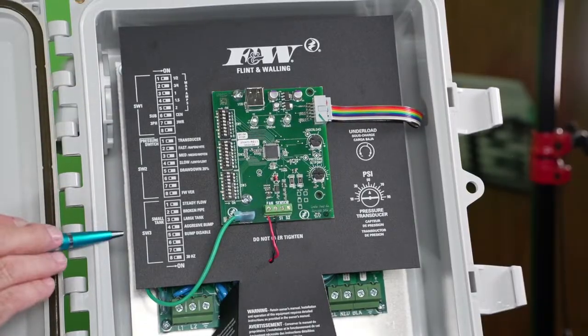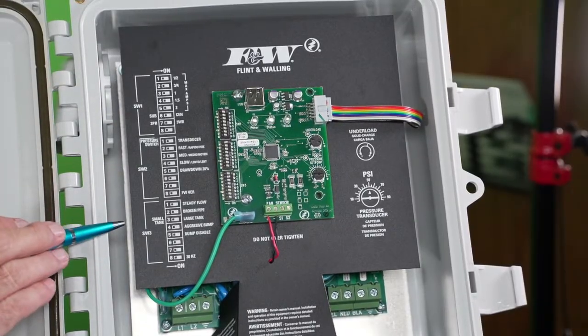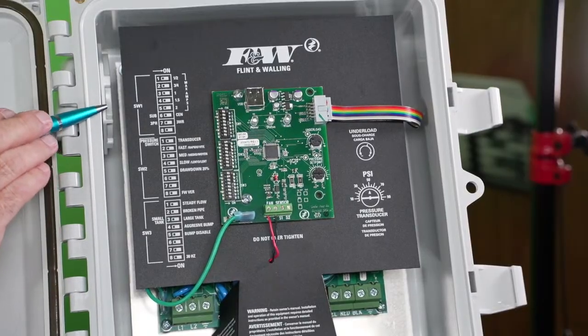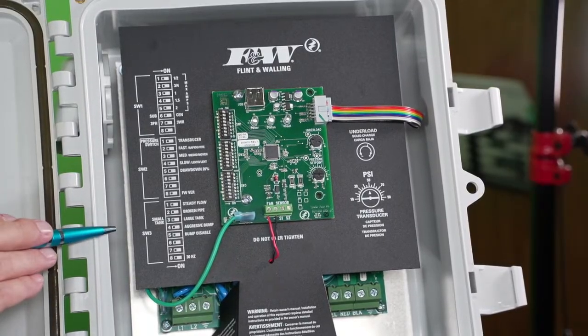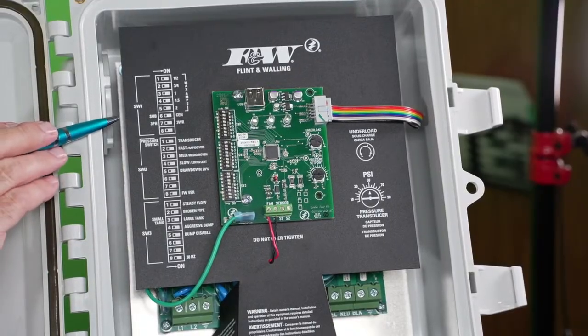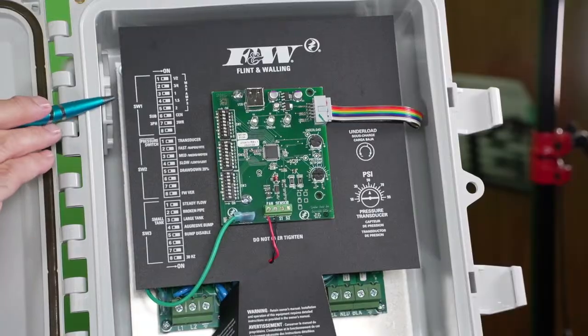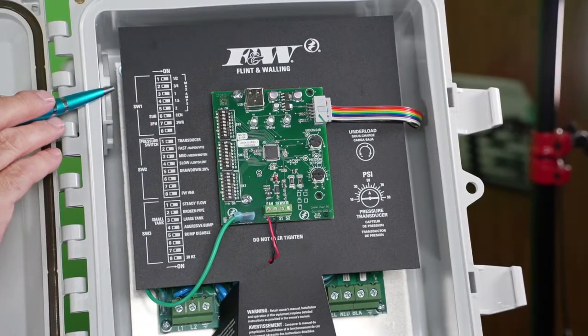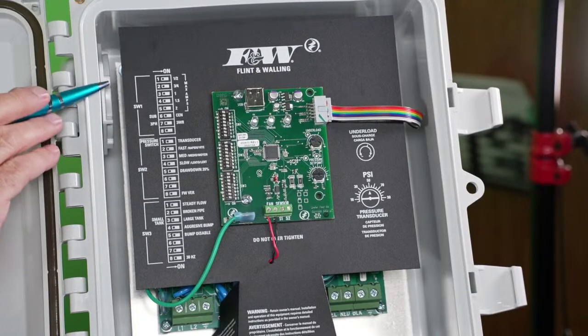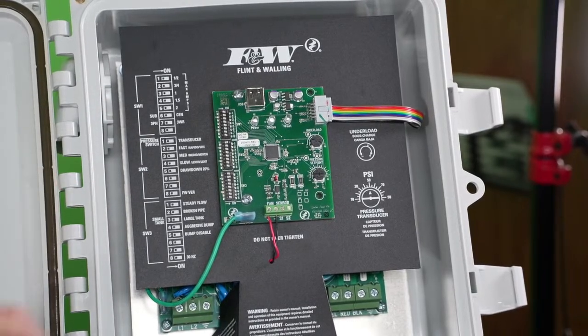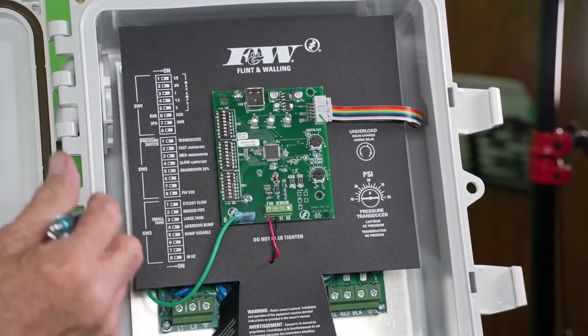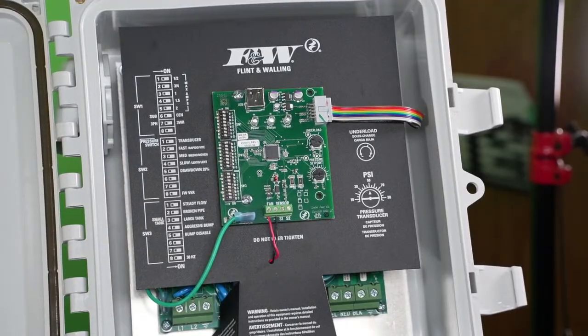But over here there are 3 banks of dip switches. The one at the top, SW1, SW2, and SW3, those 3 banks. Think of it this way. SW1, that top bank, has to do with what kind of pump you are going to operate and what the horsepower is. That's all that first bank is going to do. The second bank says how you are going to make that thing come on. We have some choices there, and I'm going to get to that shortly. But the second one is basically how you want that motor to start. And then the third bank at the bottom is kind of a catch-all, but there are some things down there that we are going to want to be aware of.